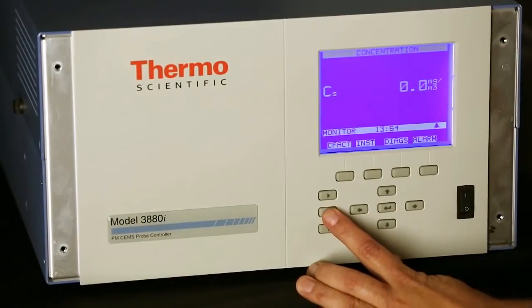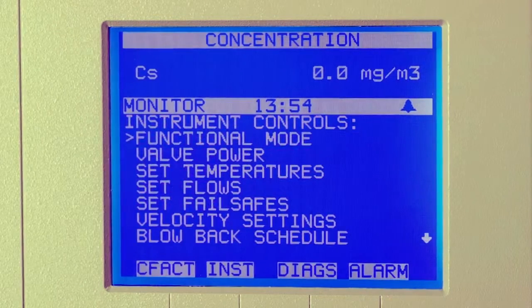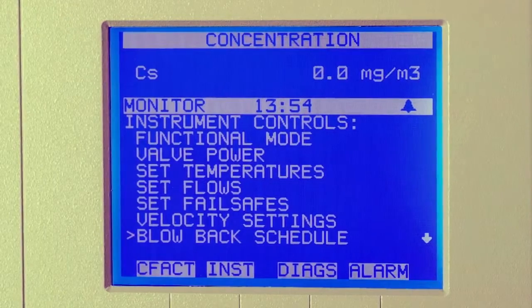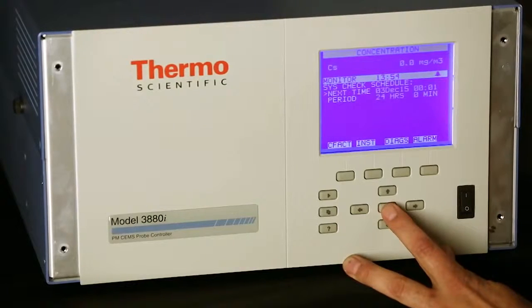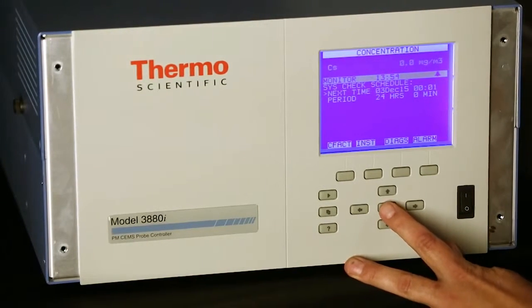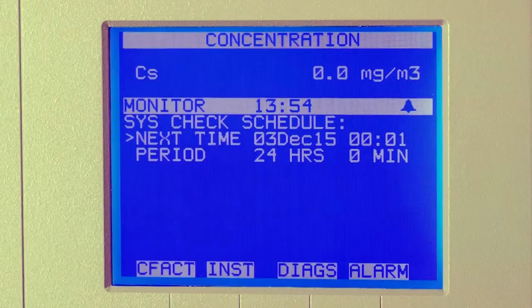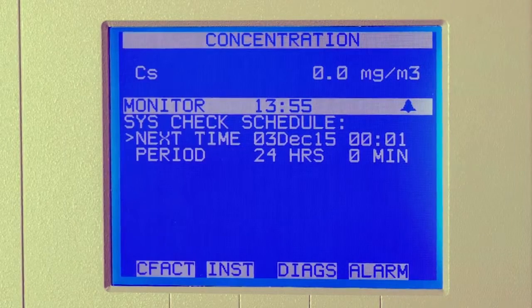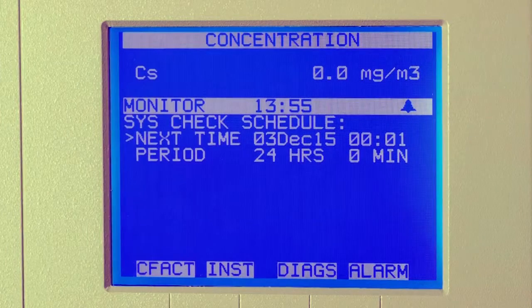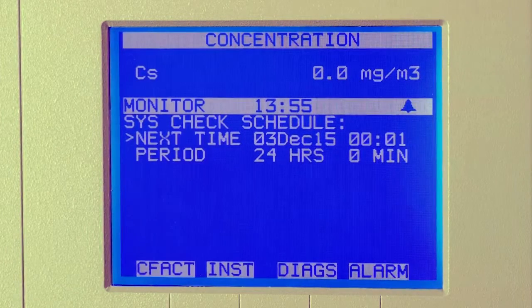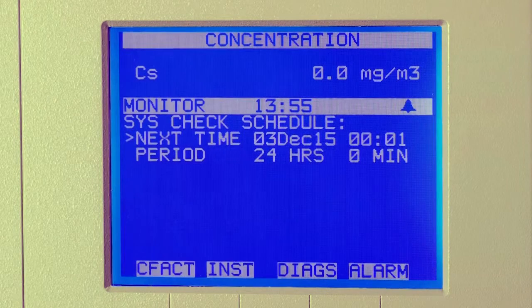To schedule an event, go to the menu, then controls, then to system check schedule. Hit enter. The schedule should be put on a 24-hour period to start at 00:01 every day. As you can see, this instrument is already set up for the next cycle. The optimum time to do the system check is during low load during the night. The system check is just a zero check to verify you have the correct set points.